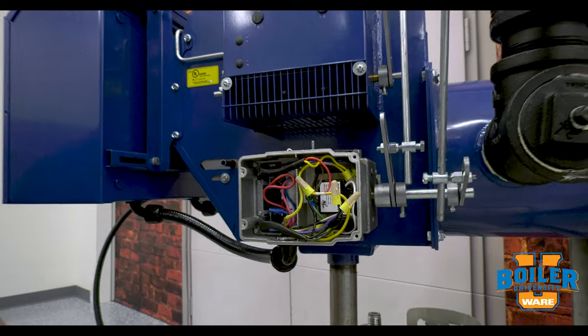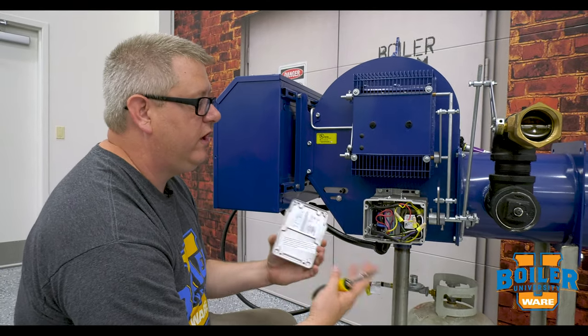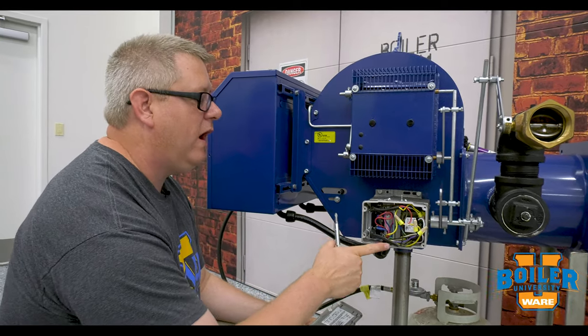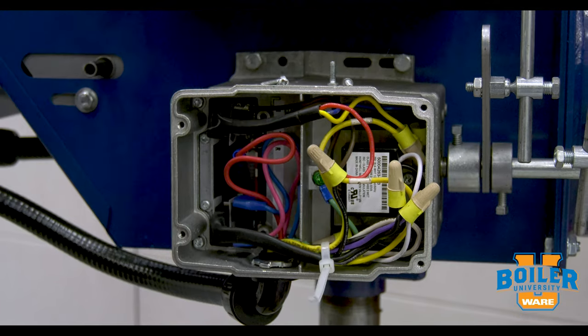What we've got here is a wire that was pinched previously, as evident by the deformation there, and we want to prevent that because that could cause a short and blow a fuse. So the proper thing to do when you've had one of these open and you're done troubleshooting is make sure to wire tie these so that they're orderly and we don't have pinching problems.